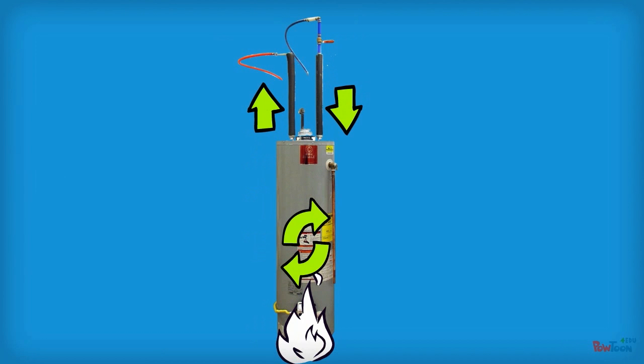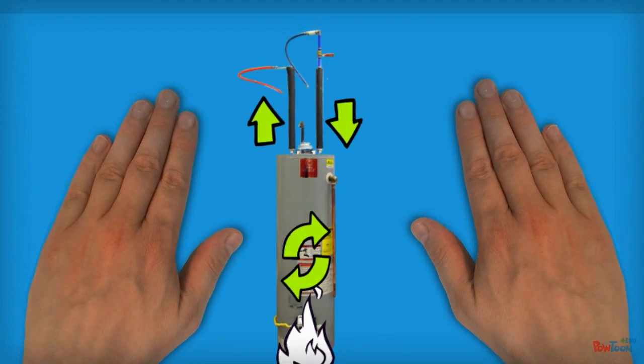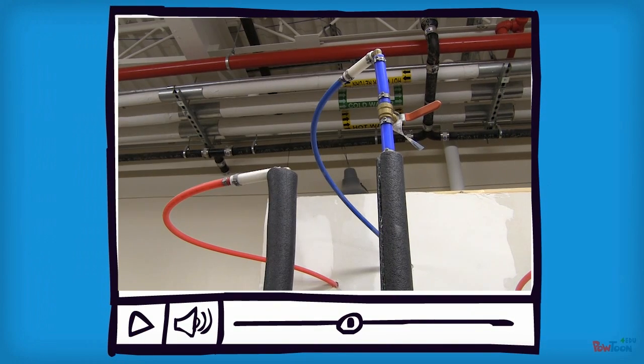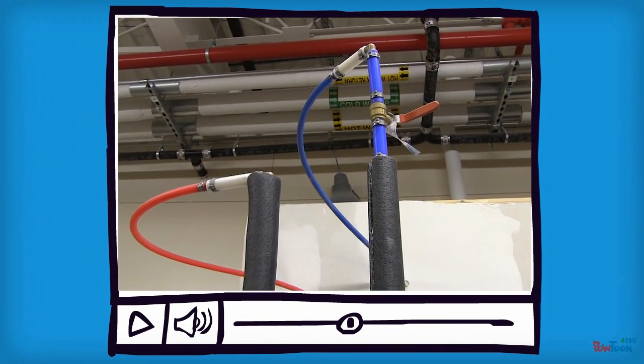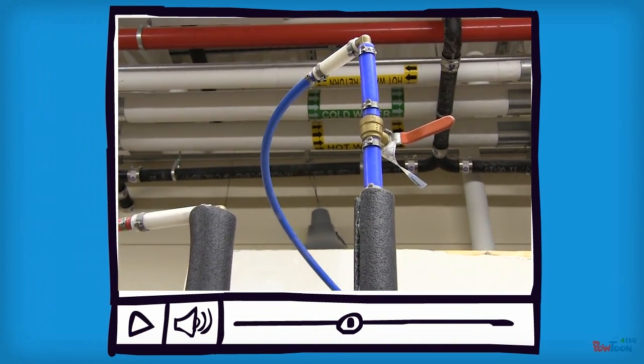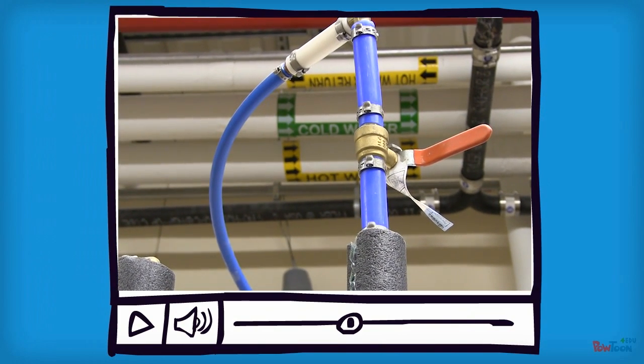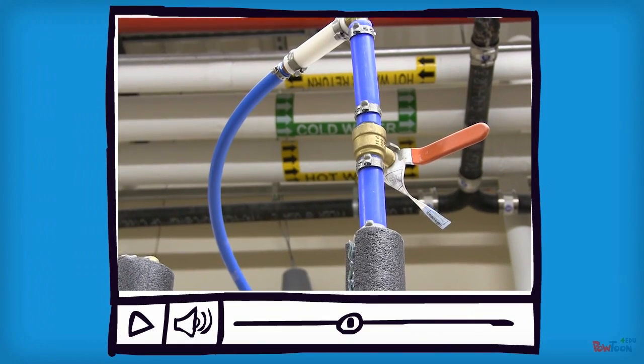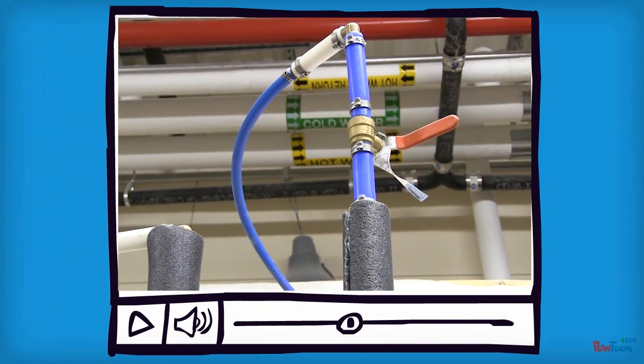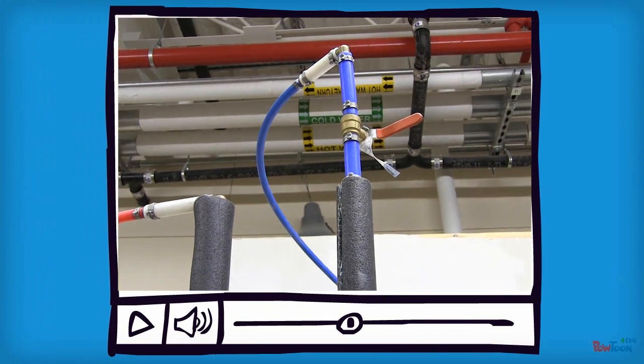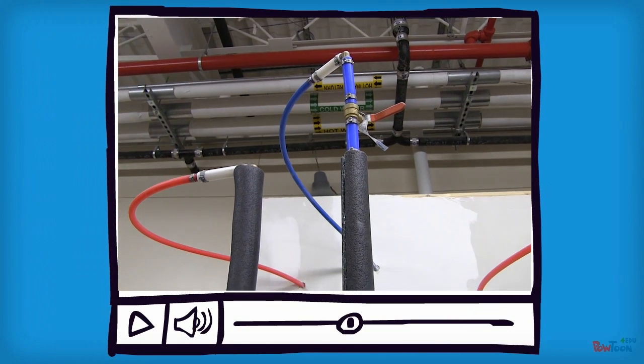Not much maintenance. The main thing you want to look at on the cold side is, okay, first of all, it needs to have a shutoff valve right above it, and that's what you need. You have to have a shutoff valve above the cold water side, so if something is wrong with the tank, I can shut the water off and drain the tank. So that's real important. Second thing is you want to look at the hot water side.